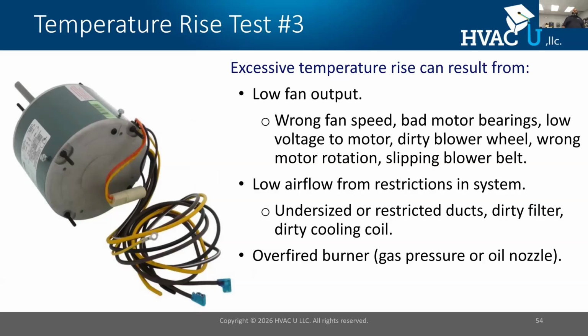Excessive temperature rise means low fan output. I've got the wrong speed, bad motor bearings, low voltage, a dirty blower wheel, or the wrong rotation or belt. Anything that's going to stop the blower wheel from turning fast enough to deliver that airflow. It can also come from restrictions and undersized ducts. That's what we're talking about today.